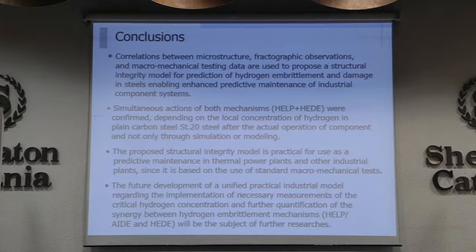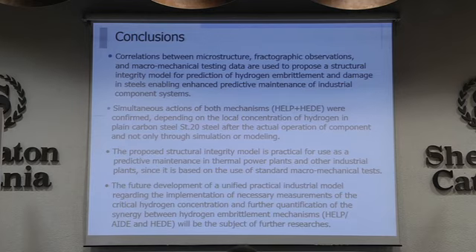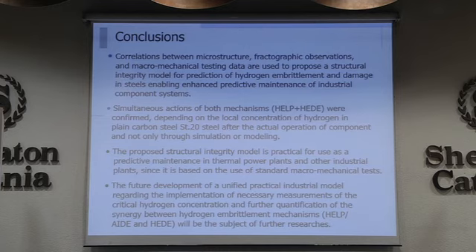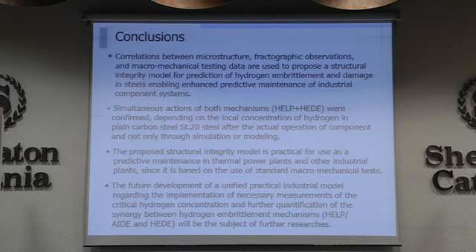The same question was raised in Norway by Professor Balich and I provided the same answer there. The proposed method is very useful because it is not complicated to perform. These results show that we can detect the damage level in the tube in its position. Also, these results reflect not only microstructural degradation — we need a very careful examination of all areas in the vicinity. We have high-temperature hydrogen attack in a very limited area, so we need careful fractographic investigation.